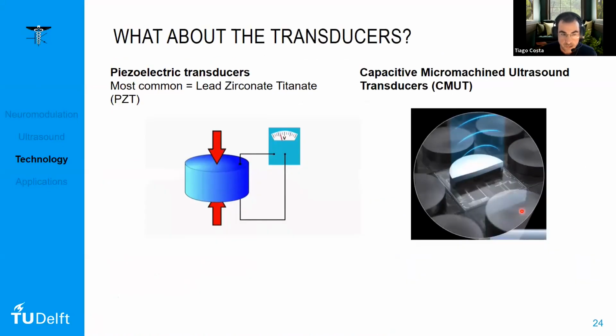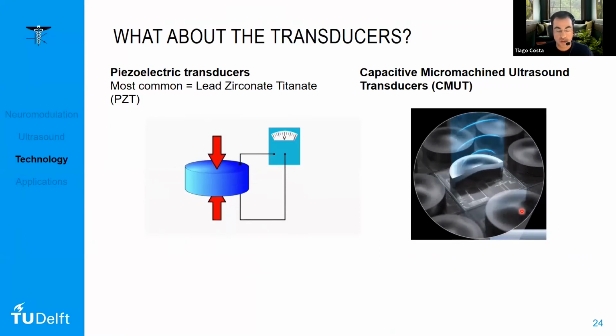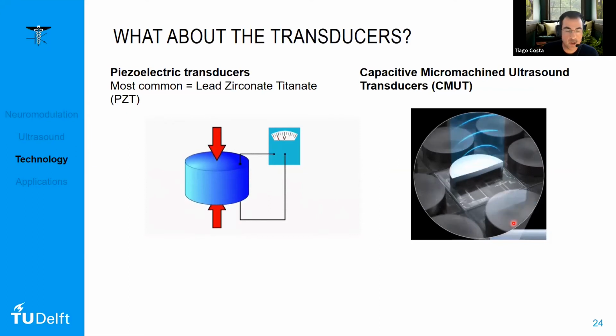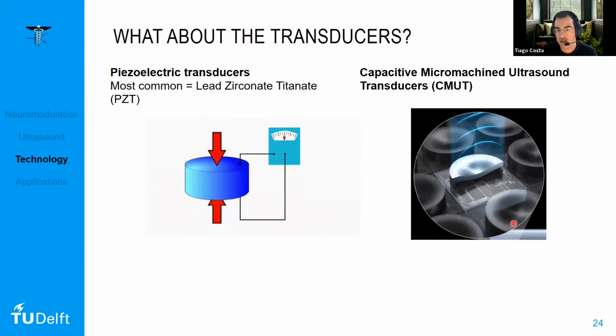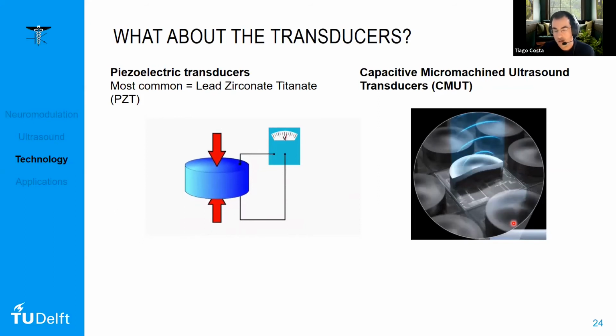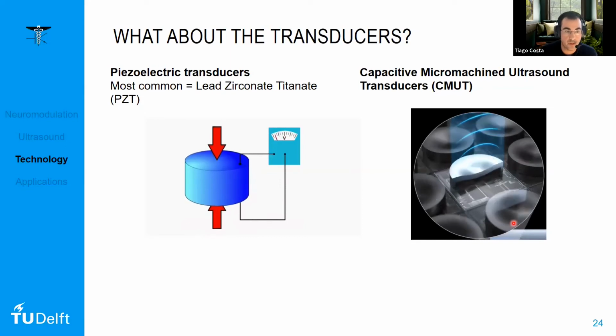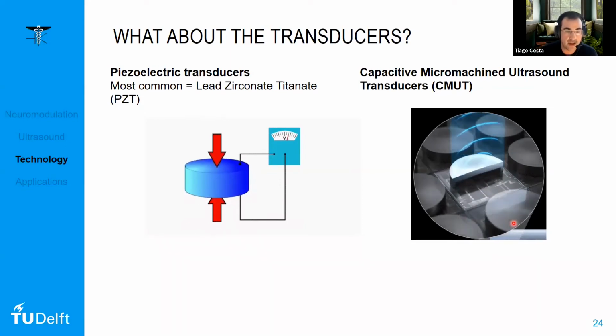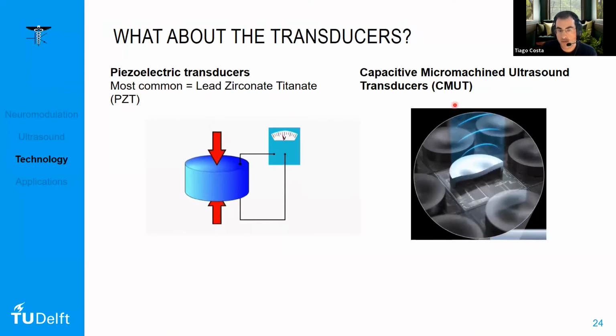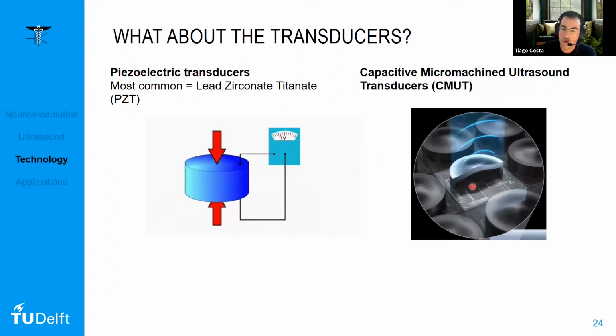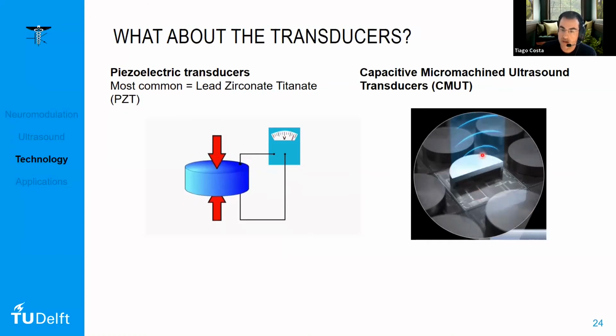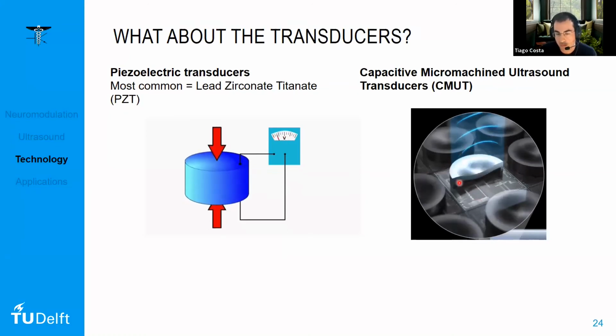And then, of course, what about the transducers, right? This needs transducers to transform these electrical signals into acoustic waves. I've been talking about piezoelectric transducers, but there are in fact two types of transducers most used for these applications, imaging and neuromodulation. Of course, based on the piezoelectric effect, most commonly PZT, lead zirconate titanate. And we also have MEMS-based transducers, in this case capacitive micromachined ultrasound transducers, where due to electrostatic forces, these very thin membranes are made to vibrate.